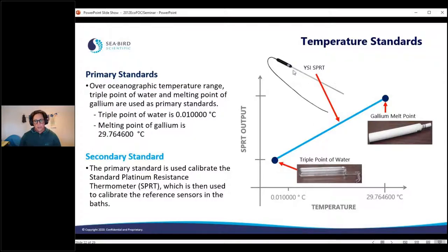The SPRT, you can see here—this isn't actually it, I couldn't find a picture online, but this is pretty much what it looks like. It has a well-known calibration curve, and if you calibrate it against the gallium melt point and the triple point of water, you can have a great calibration for it. Then you can use it to pass over to the actual sensors in the other baths. That's how we do it, and we keep these standards really, really well.